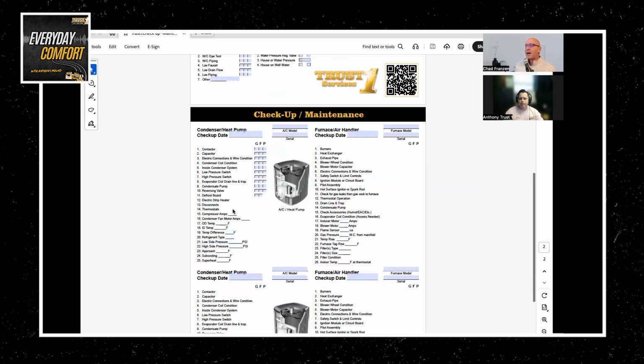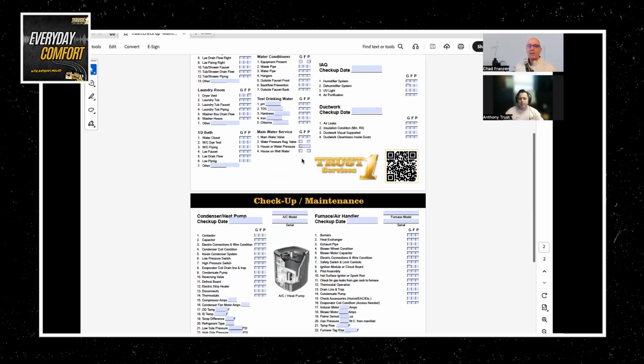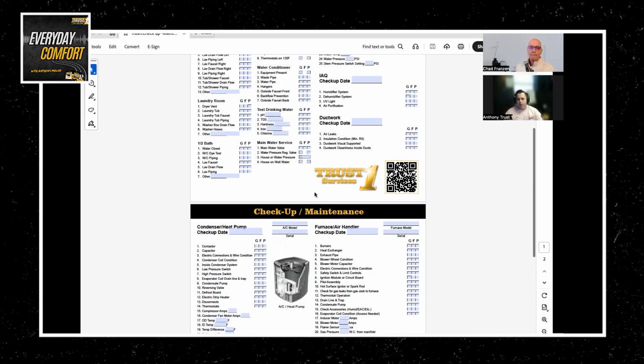So speaking of ductwork, here there's a section for air leaks, insulation, cleanliness. How much does duct condition affect comfort and energy bills? Yeah, so this is a big one for Massachusetts because we have a lot of ductwork that's been in walls for years that's unsealed, uninsulated, and then a lot of consumers now want to put in heat pumps. And what contractors may not tell them is when they put in that heat pump, they're going to lose a lot of their energy through their ductwork.